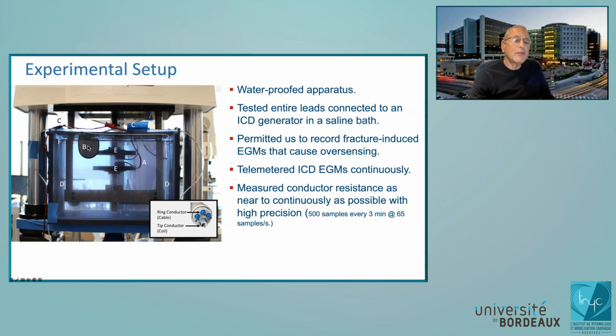We recorded these signals, then put some very high precision resistance measuring probes on to measure the resistance in the individual conductors we dissected out, recording that as frequently as we could. Then we set about breaking leads—who doesn't enjoy taking stuff and smashing it? This turned out to be a lot of work, but the good thing was we could stop this experiment at any point, take the leads off, and x-ray them to see whether anything was broken or not.